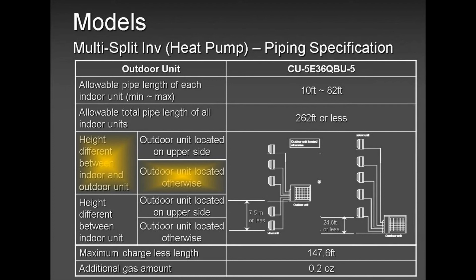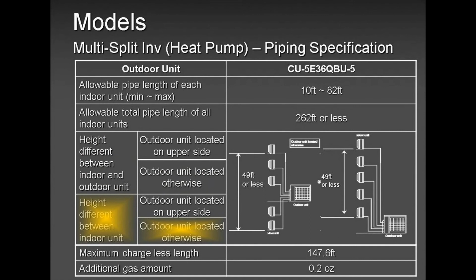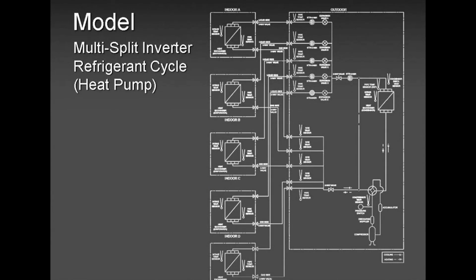aware of when the indoor unit is too high, or when the indoor unit is too low, or when the outdoor unit is too high, or when the outdoor unit is too low. At the end of the day, you will use the installation manual that came in the box, because that manual will give you the correct pipe length that you need to maintain from the outdoor unit to the furthest indoor unit, from the outdoor unit to the highest most indoor unit, or the lowest most indoor unit. Okay, so please keep that in mind.